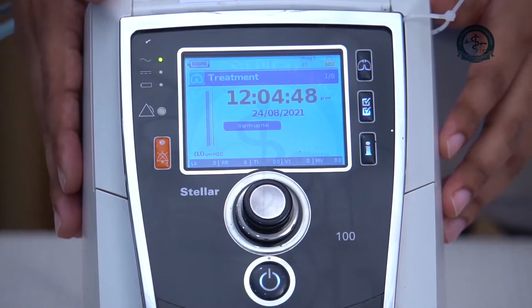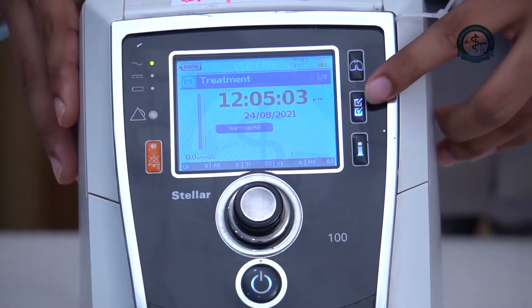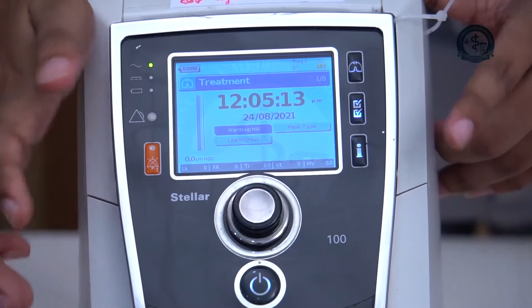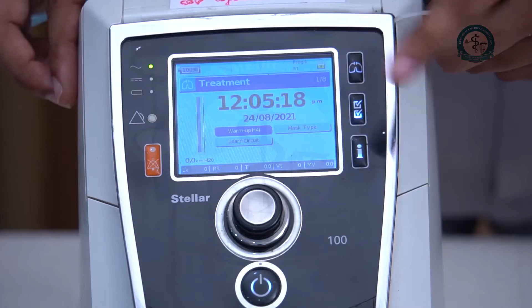Lock and unlock the main unit. Once the machine is on, you will see a locked padlock sign in the right upper corner of the main screen. You are not allowed to change settings unless you unlock the unit. To unlock the unit, press the right middle buttons which have two tick signs and the middle knob together for a few seconds. Then the unit will unlock and the locked padlock sign will change to an unlocked padlock sign in the right upper corner of the screen. Now you are permitted to change the settings.